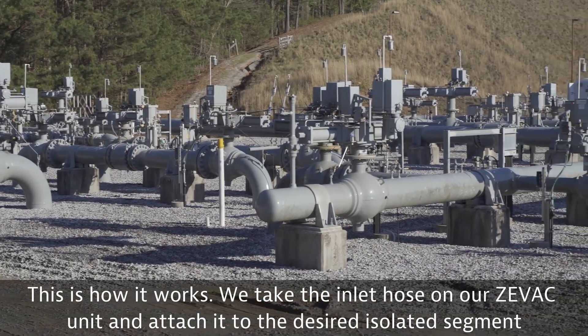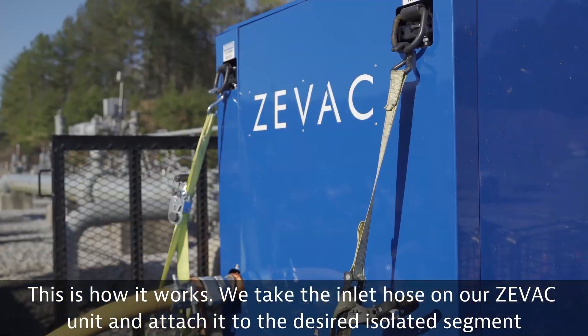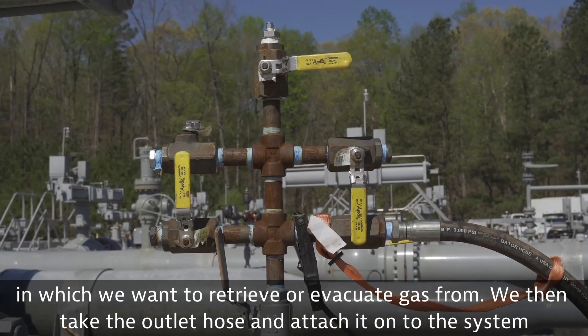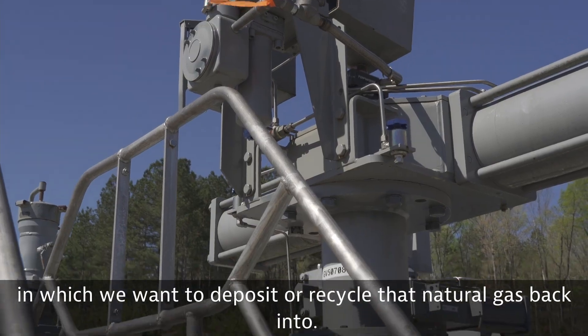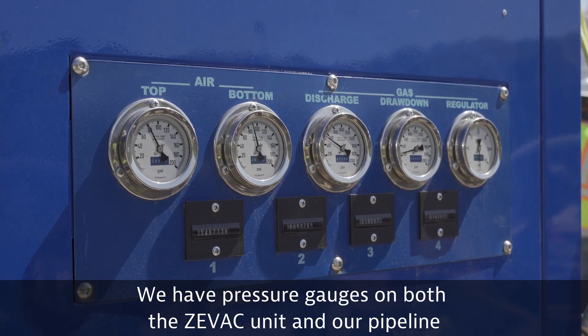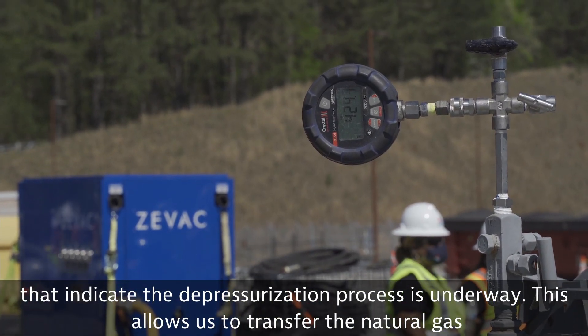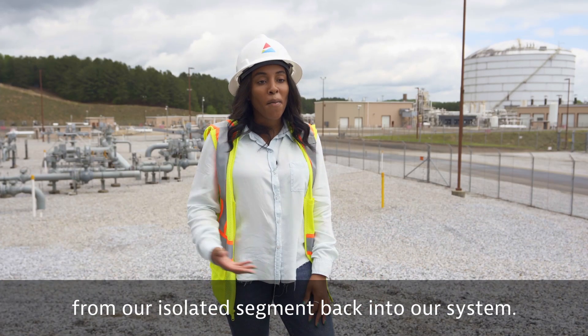This is how it works. We take the inlet hose on our ZEVAC unit and attach it to the desired isolated segment from which we want to retrieve or evacuate gas. We then take the outlet hose and attach it onto the system where we want to deposit or recycle that natural gas back into. We have pressure gauges on both the ZEVAC unit and our pipeline that indicate the depressurization process is underway. This allows us to transfer the natural gas from our isolated segment back into our system.